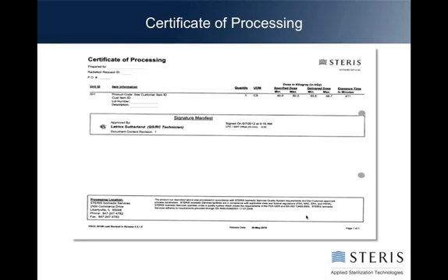Okay. There's two ways you probably have seen certificates of processing. One version is like this, but the two I'm going to show you have the same information. In one corner, you would have where it was processed, the run number for it. This one is from our Radiation Technology Center. The important thing on it is it'll have your product information, and it'll have off to the right the dose range you requested, the minimum you asked for and the maximum, and right next to it, the delivered minimum and maximum. Those are the numbers that are critical for you knowing what dose your product got, whether it be in the sterilization process or the max dose.